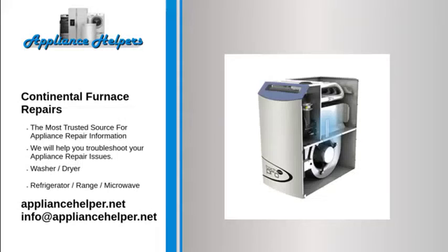On furnaces that do not use a spark igniter, does the hot surface igniter come on? You will see a bright glow in the burner compartment if it is trying to come on. If not, the igniter may need replacement or the furnace control board could be bad. Do the main burners come on? Once the pilot or igniter is on, do the main burners light?